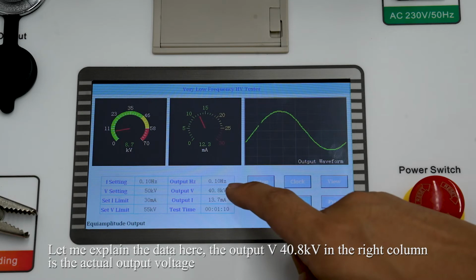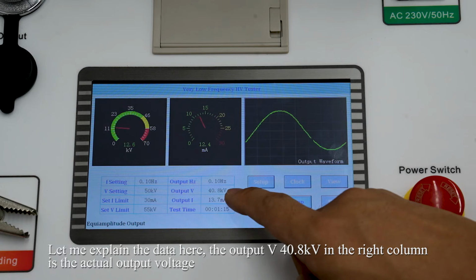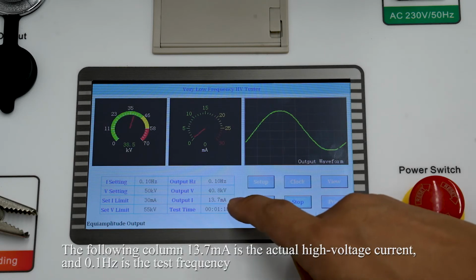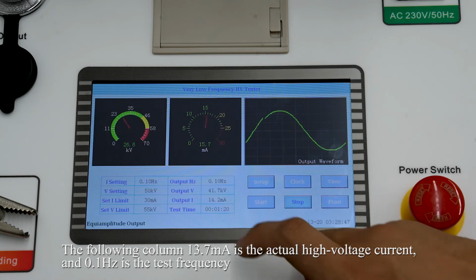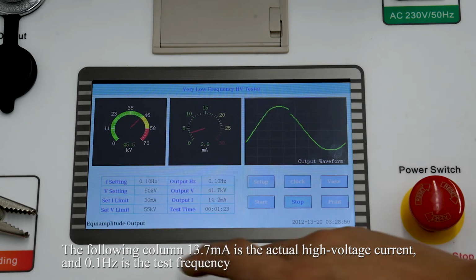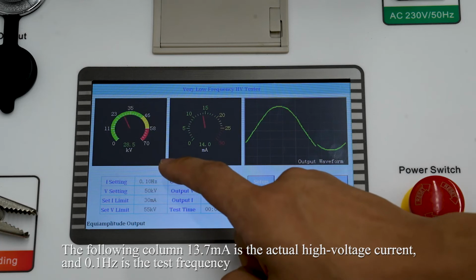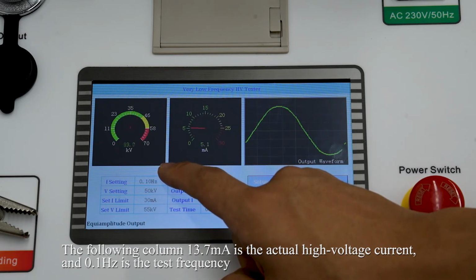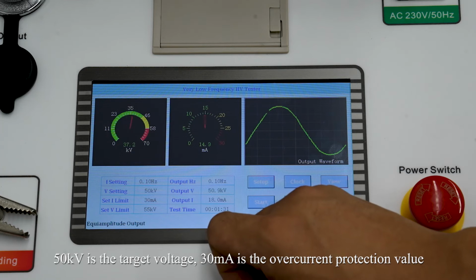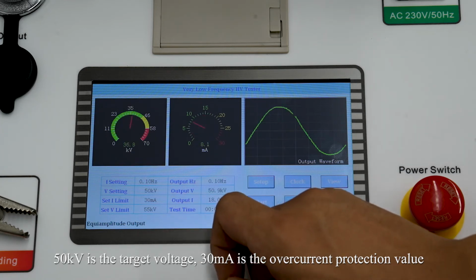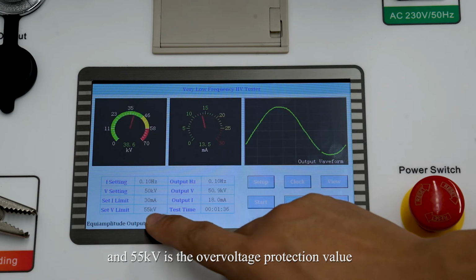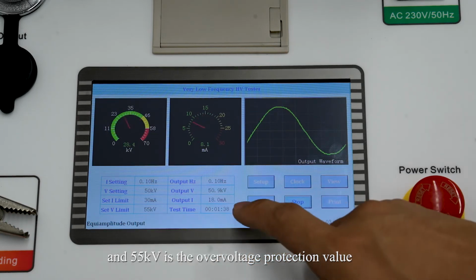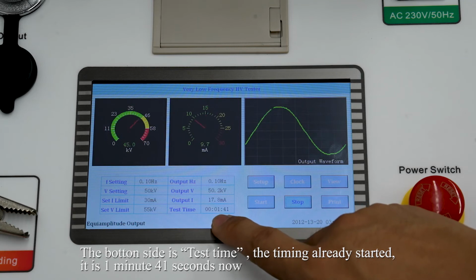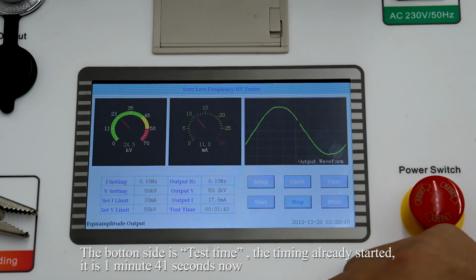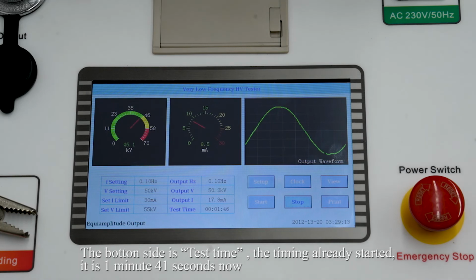Let's explain the data here. The output V, 40.8 kV in the right column, is the actual output voltage. The following column, 13.7 mA, is the actual high voltage current, and 0.1 Hz is the test frequency. 50 kV is the target voltage, 30 mA is the overcurrent protection value, and 55 kV is the overvoltage protection value. The bottom side is the test time. The timing has already started. It is 1 minute and 41 seconds now.